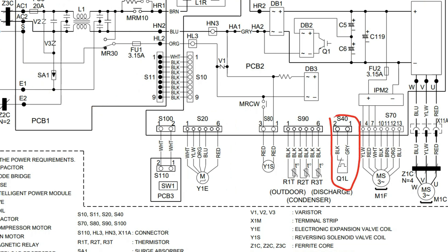Over here we have an overload protector, and another one here — those just protect components in the system from surges. I also mentioned varistors earlier — they act kind of like a shunt, doing a similar thing: any surges in the power supply get sent to earth ground. You can see there's absolutely a huge effort here to control and stabilize these circuits. The level of control is just completely obscene — the micromanagement going on. But this level of control is what gives us the ability to squeeze more and more efficiency out of the system to reach these really high SEER ratings.